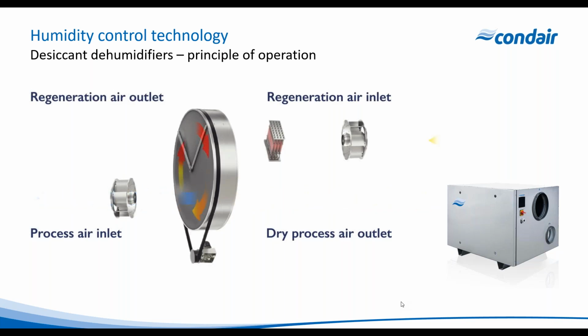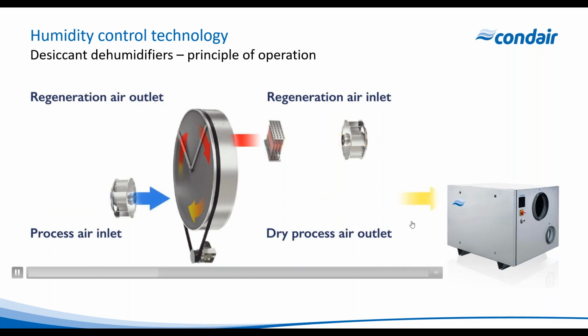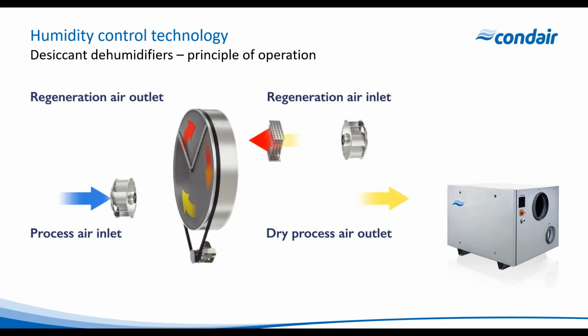If you either want to go to a lower humidity, or you've got a large HVAC system and you want to dehumidify all of the air that's going to a space, then typically you would use a desiccant dehumidifier. Now this is different again. Here you can see a picture of one, and you can see there are two ports: a supply air and a regeneration air port. So what's happening here in principle is that process air is coming in, typically from the air handling unit, and that process air hits a silica wheel, a desiccant wheel, and that captures water molecules in their gaseous state.